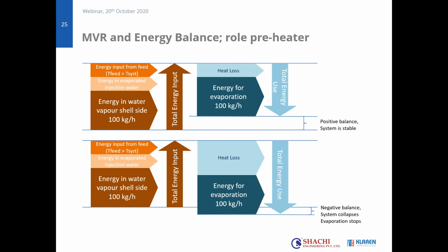Of course, this energy is used. It's used for compensating heat loss. At the end, the whole system is at a certain temperature, and it has the tendency to lose heat to the surroundings. So you lose heat. That's the first part of where the energy is used. And then the second part, which is of course what we're looking for, is we want to evaporate water. So it's the energy for evaporation of this same 100 kg of water. At the end, when the left side is larger than the right side, the system can work, because this will mean that I generate a bit more vapor. And that means that at the end, the pressure will stabilize and will settle itself so that both left and right become the same.